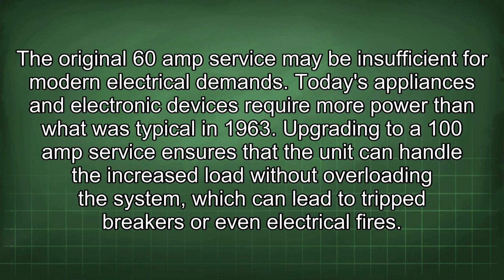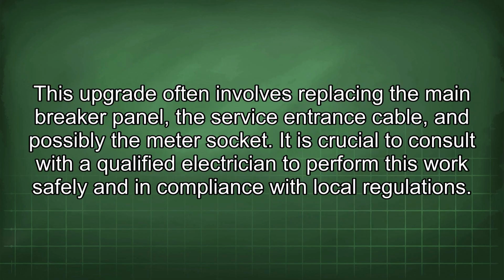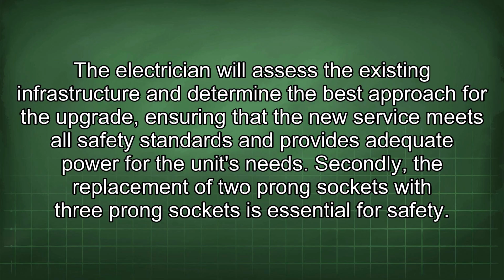Upgrading to a 100 amp service ensures that the unit can handle the increased load without overloading the system, which can lead to tripped breakers or even electrical fires. This upgrade often involves replacing the main breaker panel, the service entrance cable, and possibly the meter socket. It is crucial to consult with a qualified electrician to perform this work safely and in compliance with local regulations. The electrician will assess the existing infrastructure and determine the best approach for the upgrade, ensuring that the new service meets all safety standards and provides adequate power for the unit's needs.